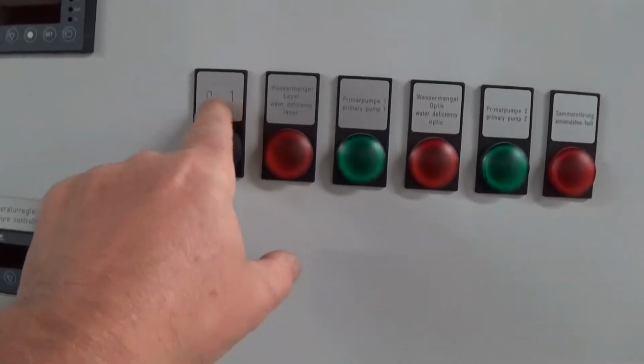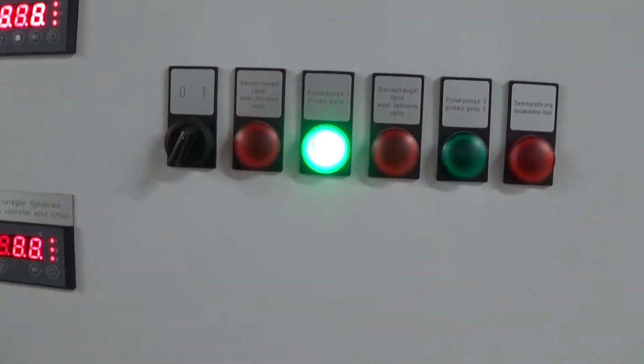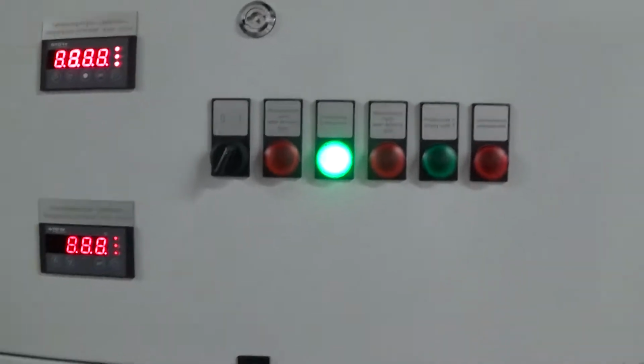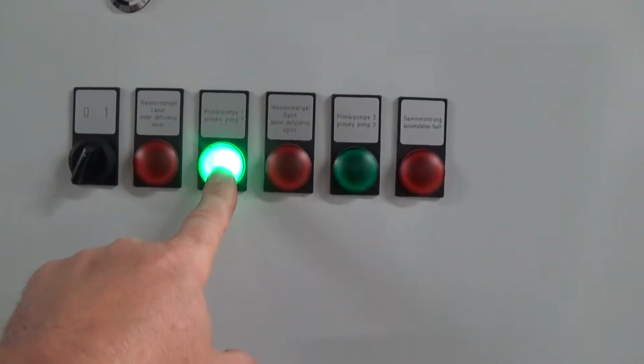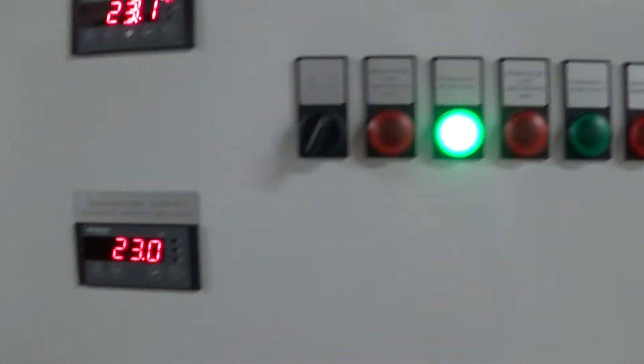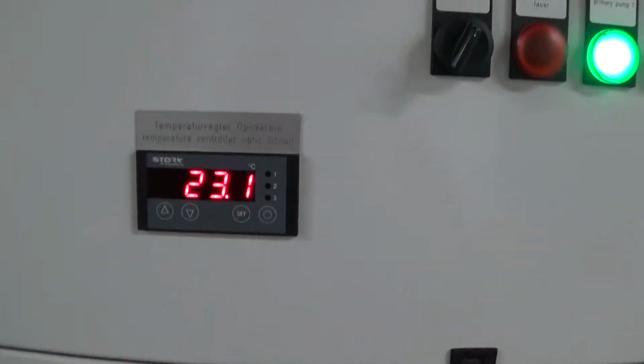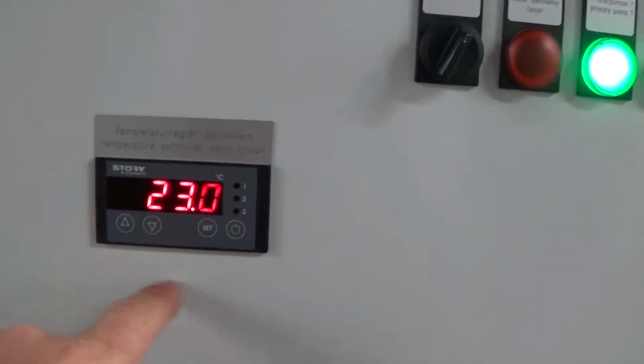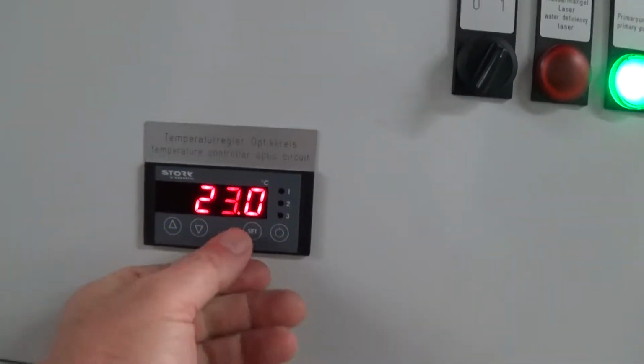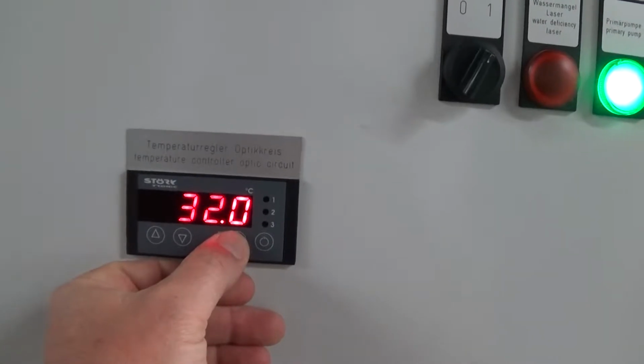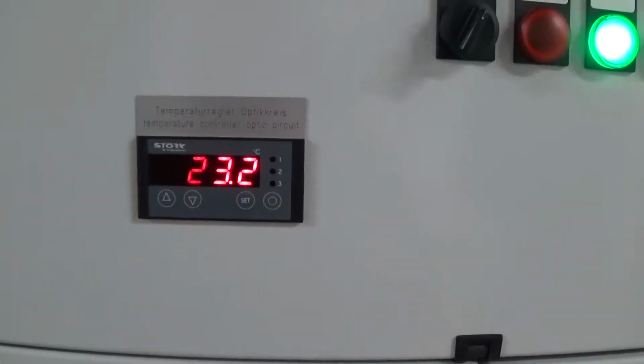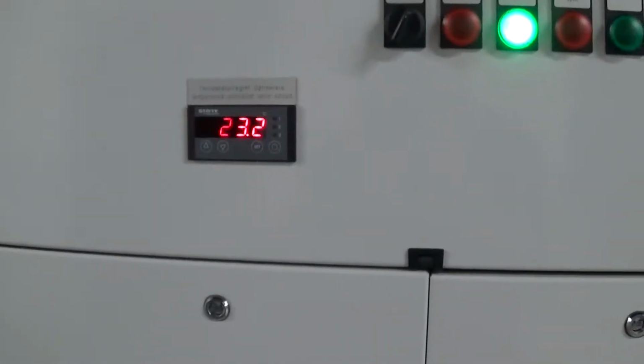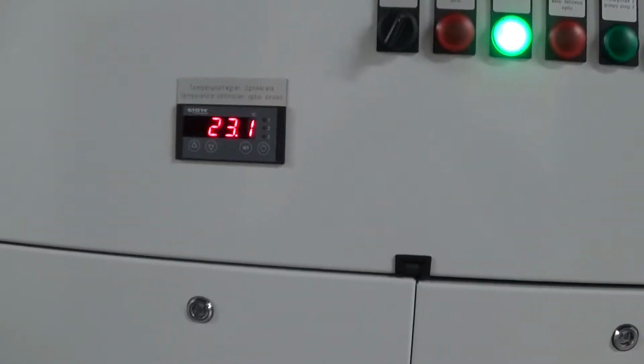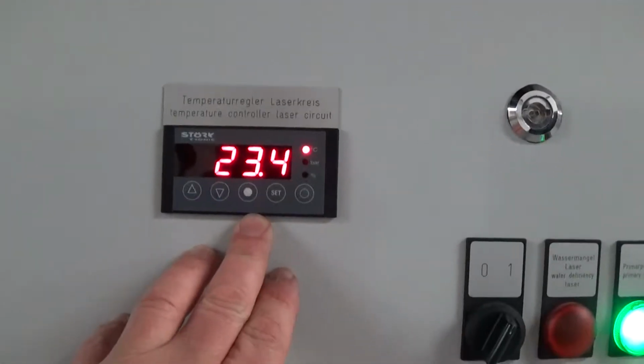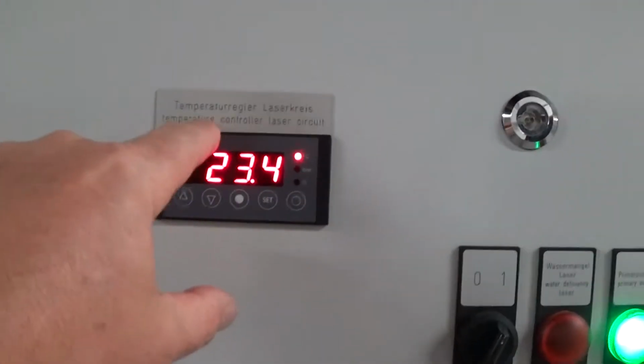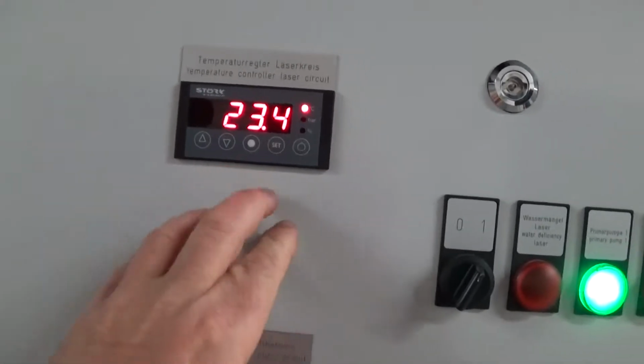So this is simply your 0-1, your on-off power for pump number 1. Green light should come on and stay on. So you have 2 controller circuits here. The lower one is the optic circuit. Even though that will still read power, you don't need to touch it. You can just leave it set at 32. But basically that's just sensing air in that small little optics DI tank that's not going to be used. It's the upper one here, they call the laser circuit, that's your primary water circuit.